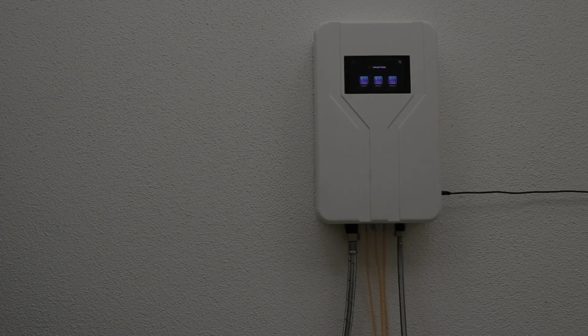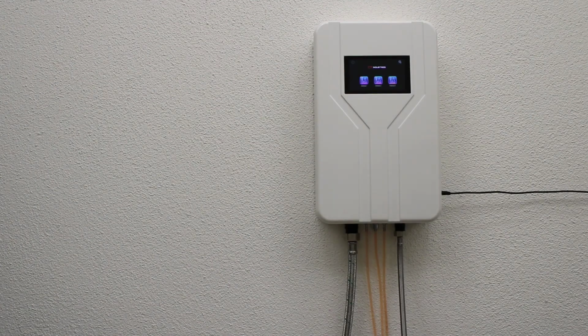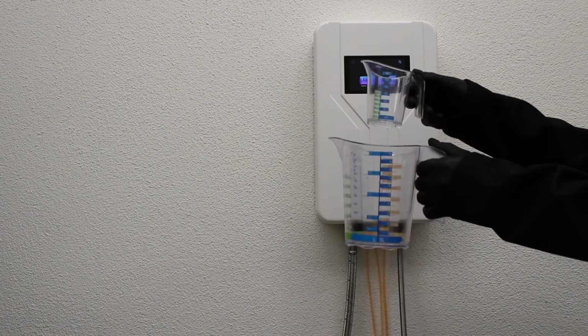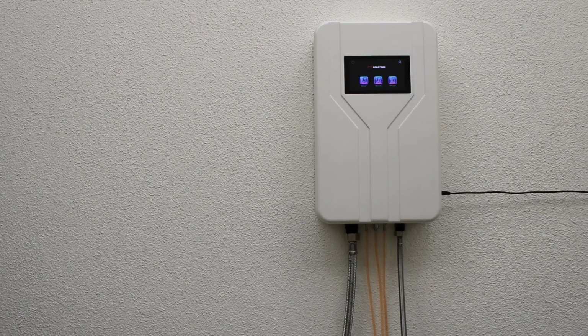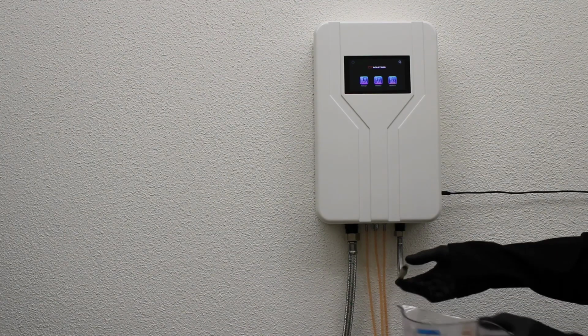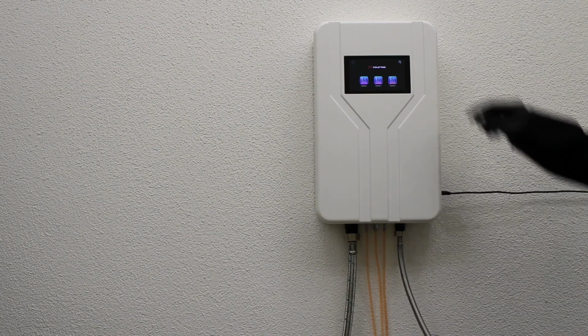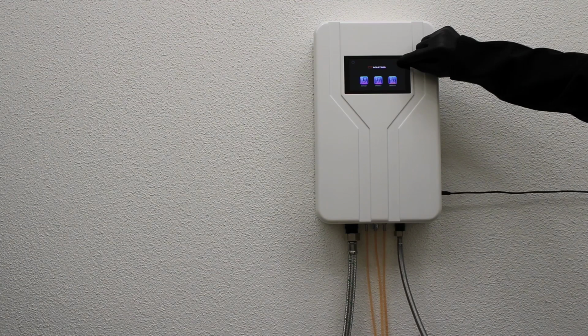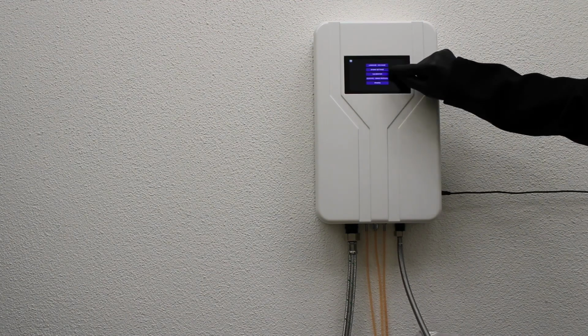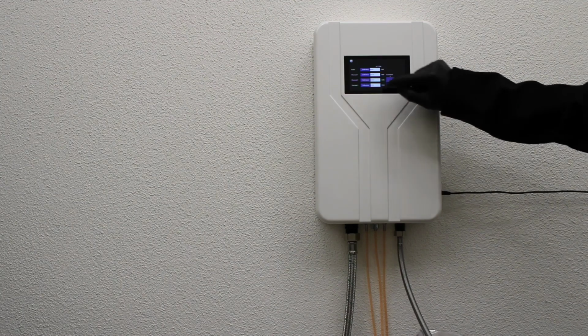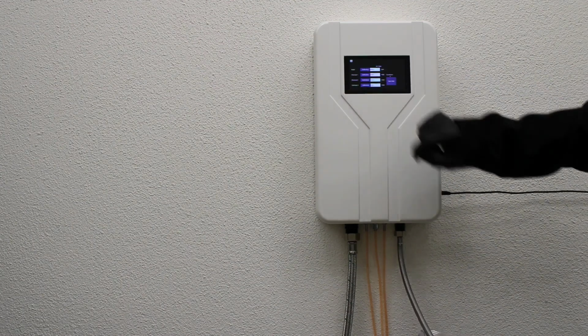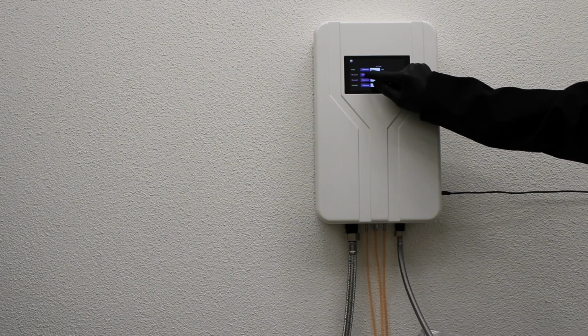Calibrating chemicals. To perform the chemical calibration, you will need a container with a capacity of at least 1 liter and a measuring cup with a capacity of at least 0.5 liters. First, take the container and place the output hose of the dosing system into the container. Then, press the Settings button located at the top right of the display. In the list, you will find the calibration option. In the second line, you will see the calibration for chemical 1.